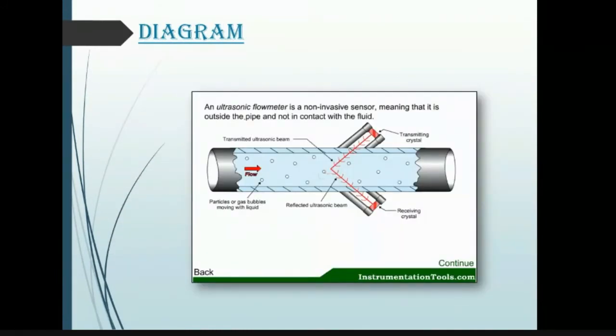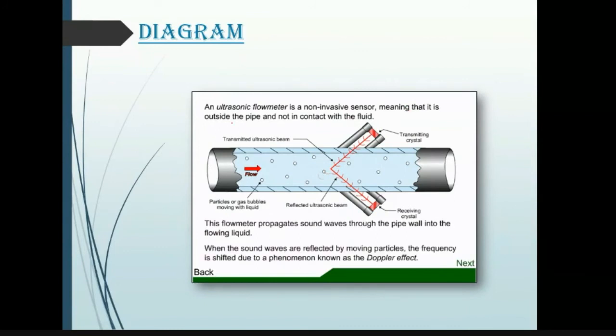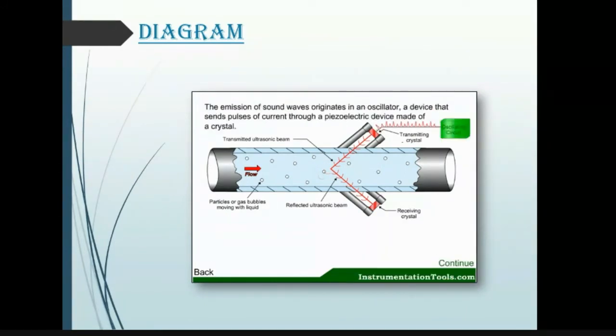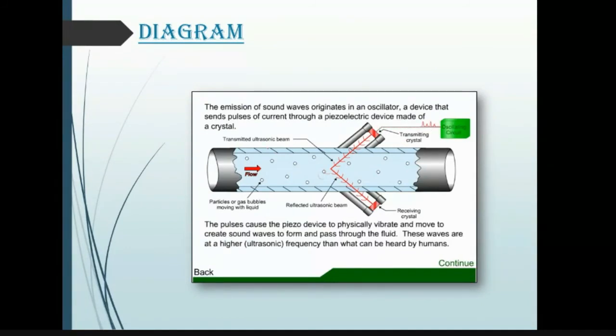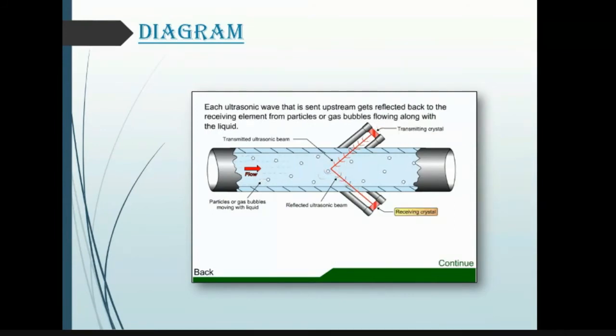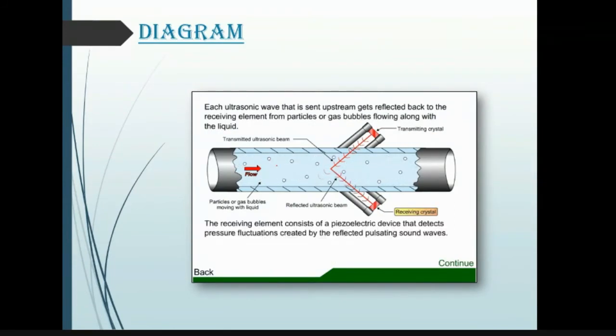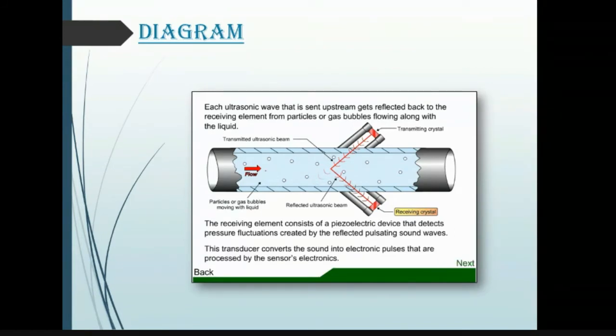Now here, an ultrasonic flow meter is a non-invasive sensor, meaning that it is outside the pipe and not in contact with the fluid. Here we can see there is a transmitting crystal and a receiving crystal, and then a transmitted ultrasonic beam and a reflected ultrasonic beam. And there are particles or gas bubbles moving within the liquid. If there are no particles within the liquid, we will not be able to measure any velocity.